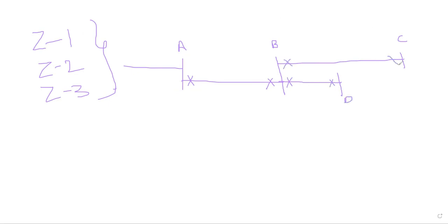So let's assume this is my A substation, this is my B substation, this is the C substation, and this is one more substation, the D substation. We have breakers here. This is the breaker. This is the breaker. I want to protect this line. So how I will do it is I will consider 80% of the line under Zone 1. 80% of the line should be covered in Zone 1.